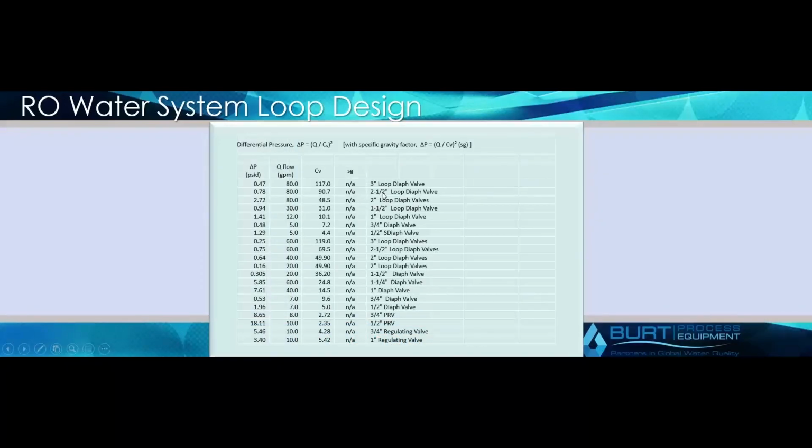And obviously the pressure loss across it as well. It is worth noting you do have a pressure loss in your RODI system as well, which can actually be quite a bit. So if you have distribution where you're going to have filters, UVs, DI beds, you could lose 30 pounds just going through the distribution of your system, plus your loop, plus all of your different valving.